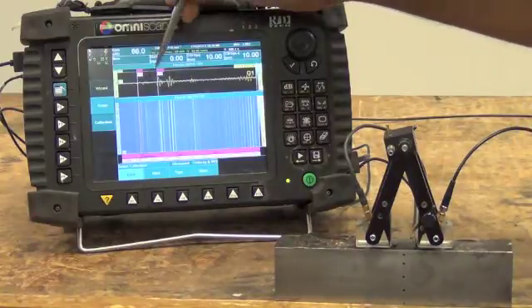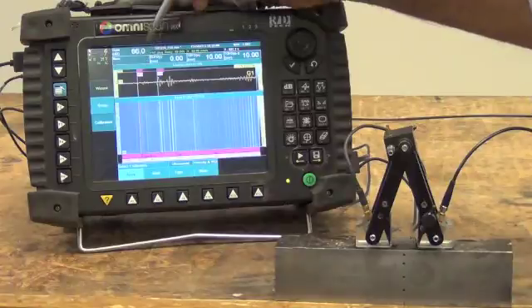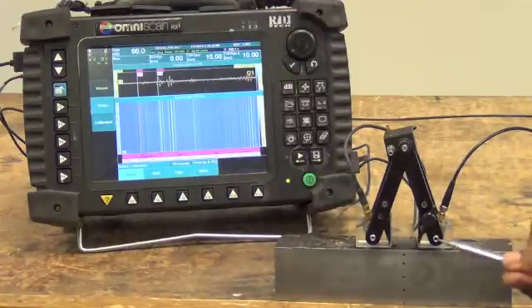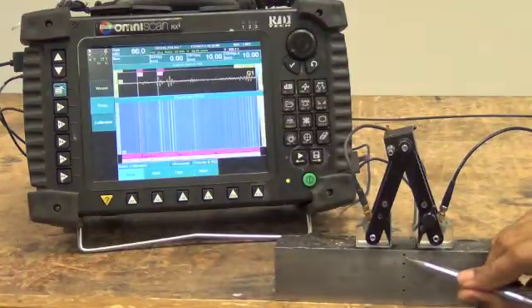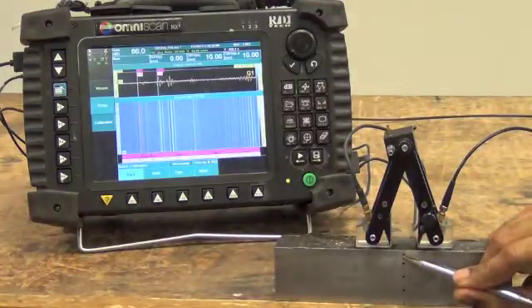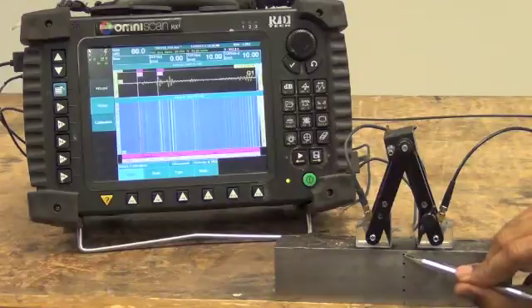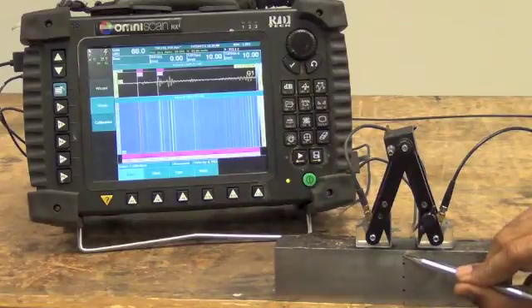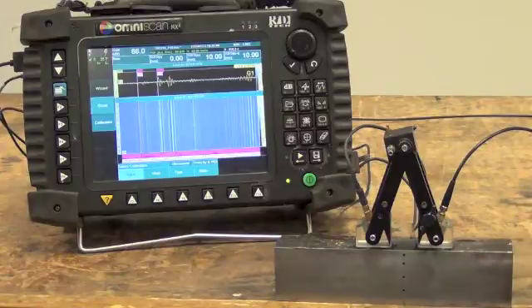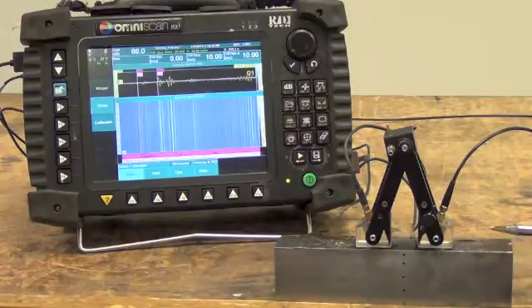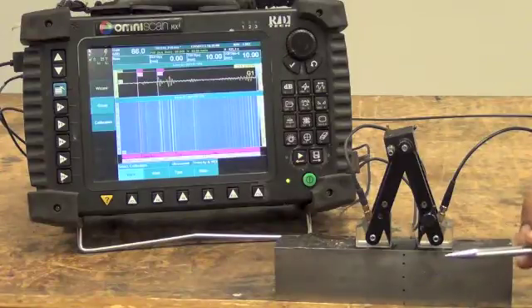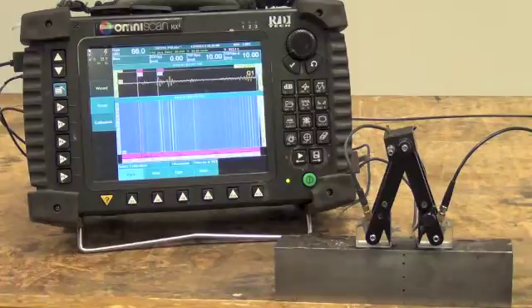What we can see is that we are unable to see the top hole which is right here at 4mm. The reason for that is that it is in the top dead zone, which is the zone which is shadowed by the lateral wave.